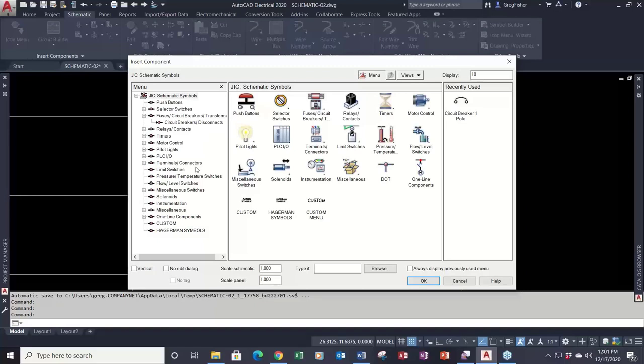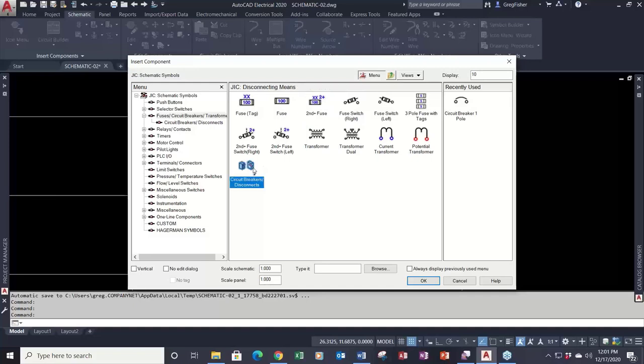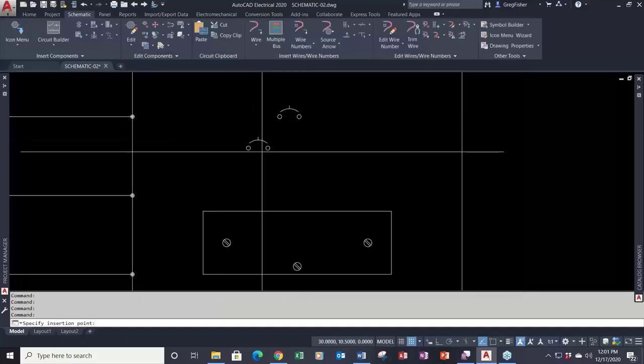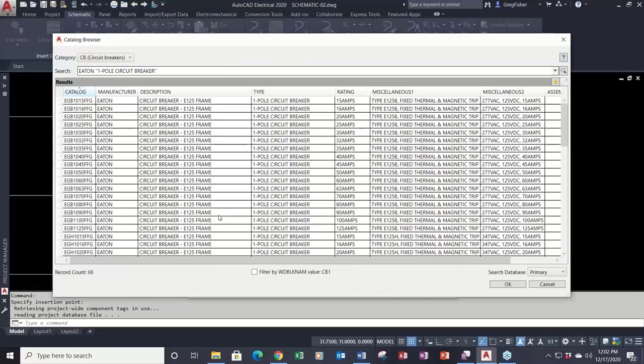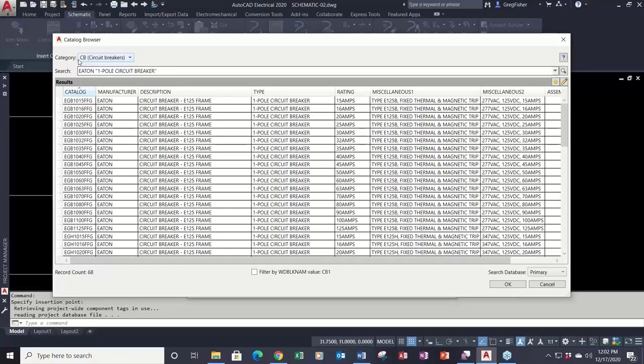In the parts database, you should think about the parts database before you even create a new schematic symbol. As an example, I'm going to create a simple single pole circuit breaker. Under the catalog data, when I hit the lookup button, it goes to a category called CB. This category is an attribute in the symbol called the family code, and that's why it's so important that you know your family code before you start your first line of a symbol.